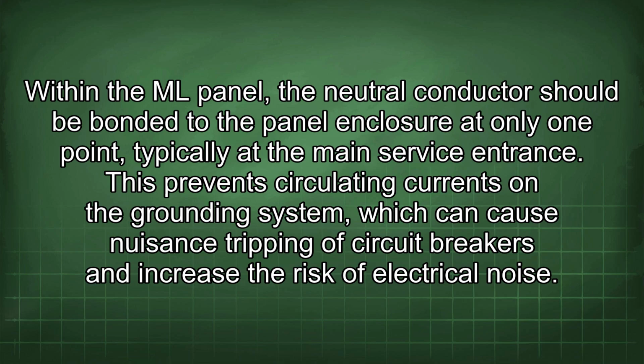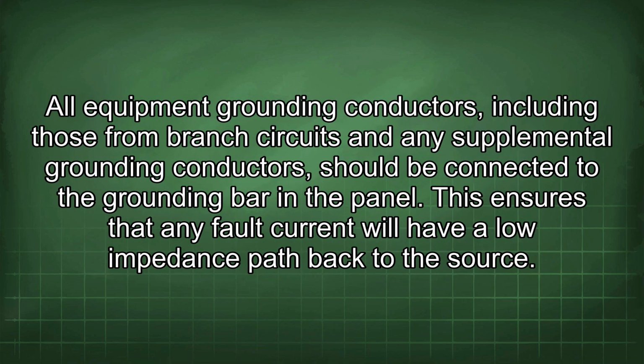Within the ML panel, the neutral conductor should be bonded to the panel enclosure at only one point, typically at the main service entrance. This prevents circulating currents on the grounding system, which can cause nuisance tripping of circuit breakers and increase the risk of electrical noise. All equipment grounding conductors, including those from branch circuits and any supplemental grounding conductors, should be connected to the grounding bar in the panel. This ensures that any fault current will have a low impedance path back to the source.